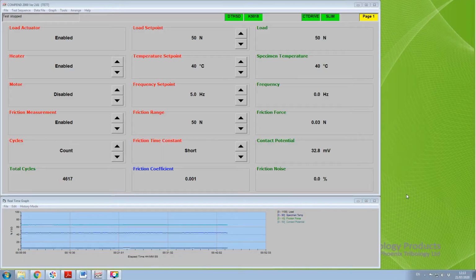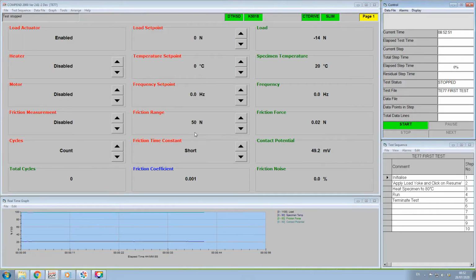Clicking on Test Sequence on the toolbar presents a menu allowing the user either to create a new 10 or 20-step test sequence file, or alternatively to open an existing test sequence file. Selecting an existing file and clicking Open generates two new windows. The upper window is Control, which is used to start and stop the test, and also to create a data file. The lower window is Test Sequence, which is used to view and edit the test sequence file.